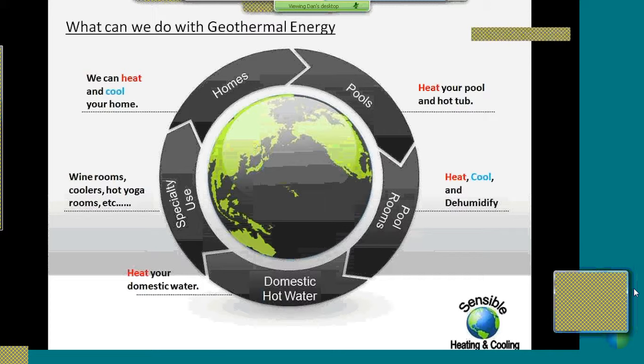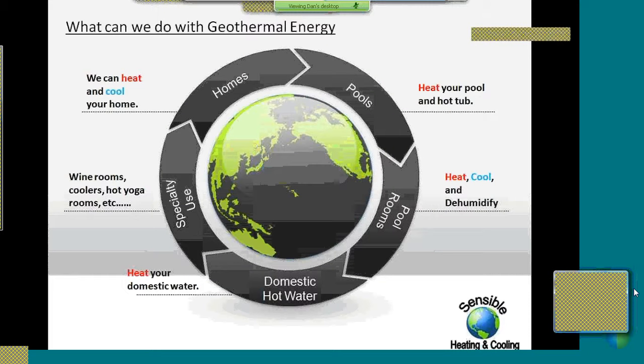We can make domestic hot water with geothermal energy. There's an option for geothermal heat pumps called a de-superheater, which basically preheats your domestic hot water. The way it does it is, anytime you're cooling or heating, especially in cooling, there's a byproduct of that process, which is extra heat, extra energy. So we want to do something with that. What we do is take that energy anytime we're heating or cooling and put it in a preheat tank for your standard water heater. It makes heating your domestic water very, very cheap.